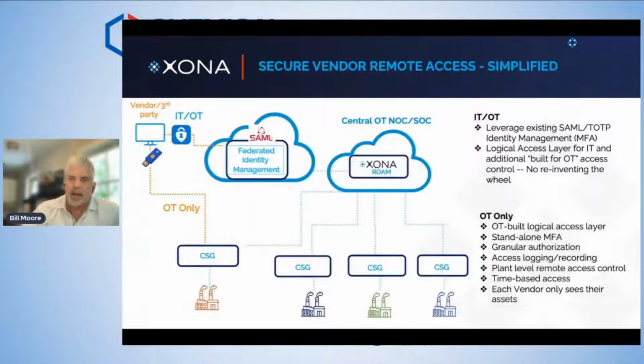To break this down, there are a couple of different ways a vendor could come into a critical power plant, for instance. One is through the IT/OT network. A lot of things are moving towards federated identity management, SAML 2.0, tools like Okta and so forth, federating that on the IT side. Then you would come into maybe an OT NOC or SOC, and there may be another level of multi-factor authentication to get down to our CSG, or critical system gateway, which is the last policy enforcement point before getting to that HMI in the control room, the engineering workstation, SCADA application, or whatever it may be. So that's one way, and it's really not trying to reinvent the wheel on the IT side, just adding additional layers of strong authentication and granular authorization to those systems.